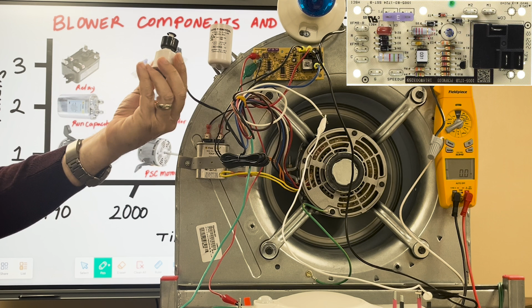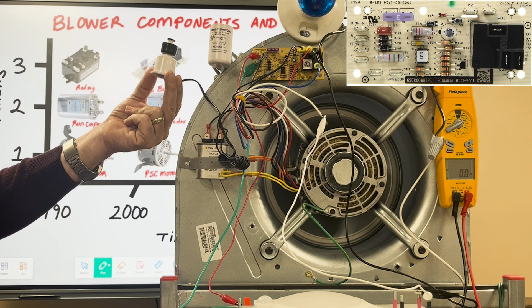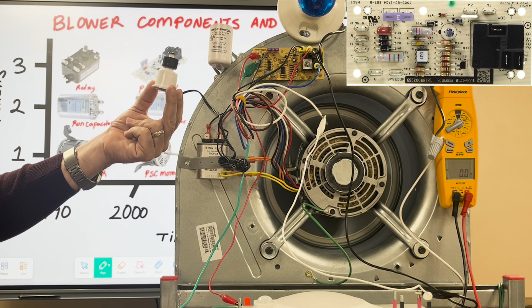And if I were to have any type of power interruption here, I'm just going to turn my float switch upside down. This will break that G call. And there is a time delay on off. Now there's a 7-second time delay on, right? But there's a 65 to 80 second time delay on the off cycle. So once we hit that 65, 70 seconds, 75 seconds, then the motor will shut off. You'll see the light come on because, as I said, there's always going to be power on that terminal when the relay's in the open position, because this is on the normally closed side.